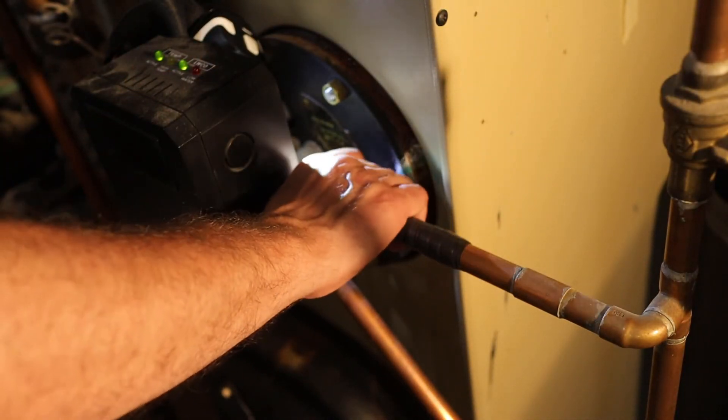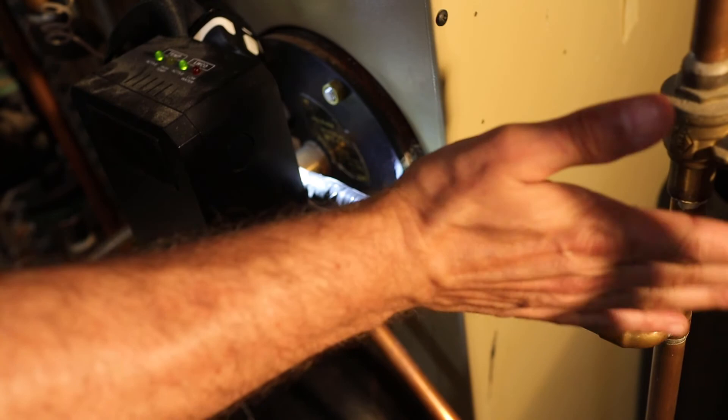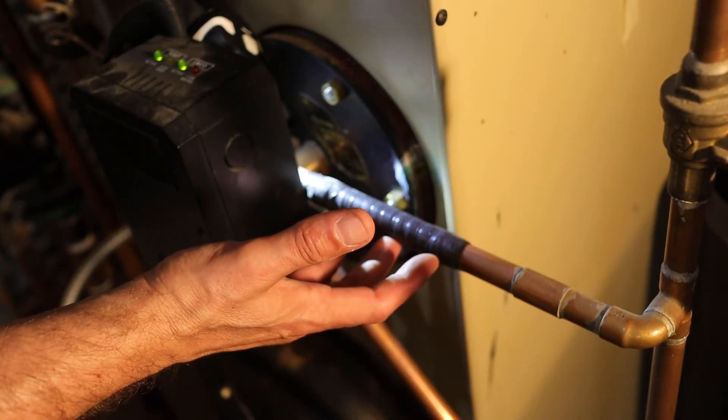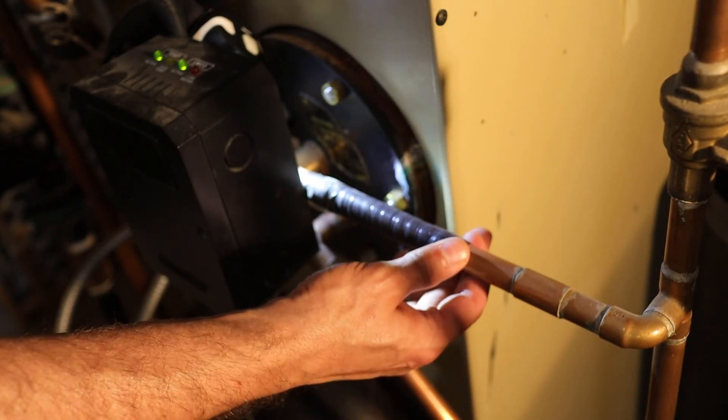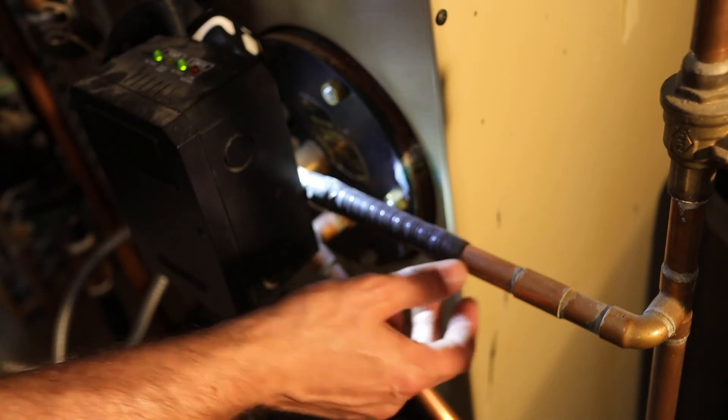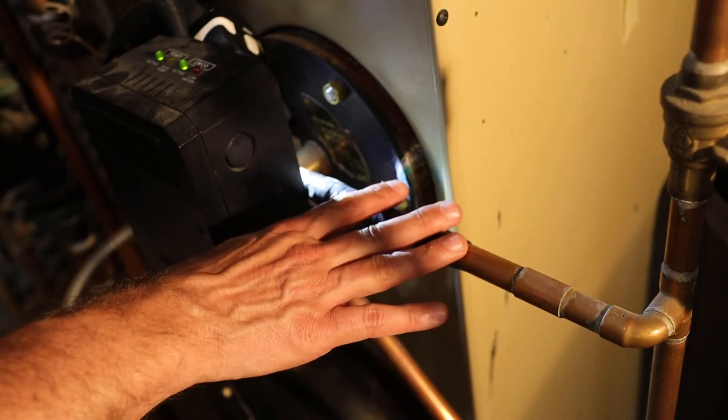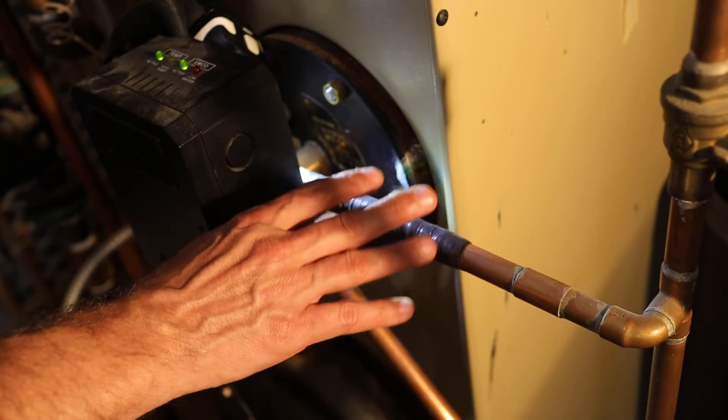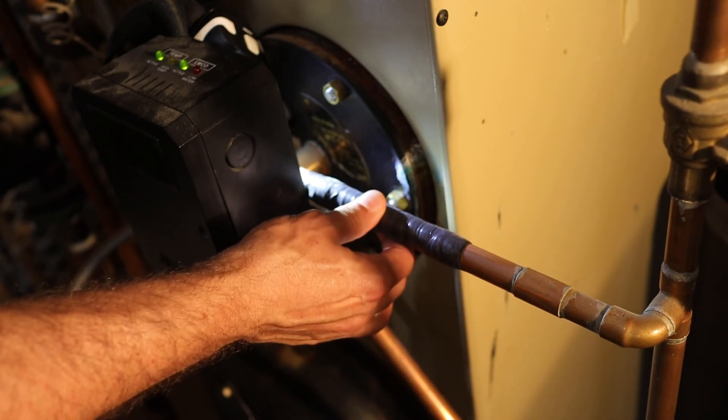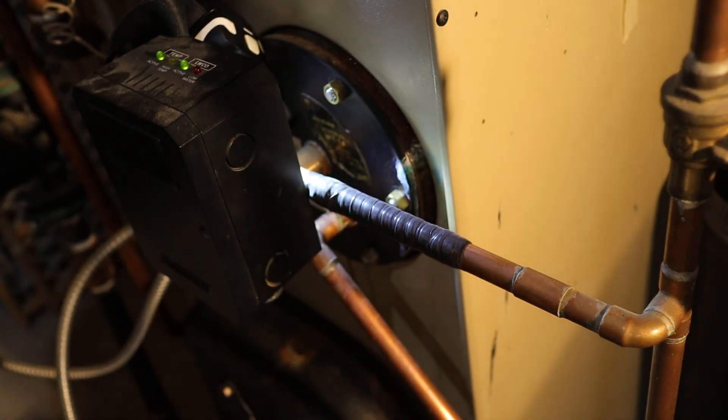It's been about 45 minutes. The tape feels like it's fully cured, so I turn the water back on to get full pressure into here. And so far, I'm not seeing any signs of any leaking, either where the leak was here or at the ends of the tape. I'll keep an eye on this for a little while longer, but I think this is going to solve the problem for now until I can get this pipe replaced.